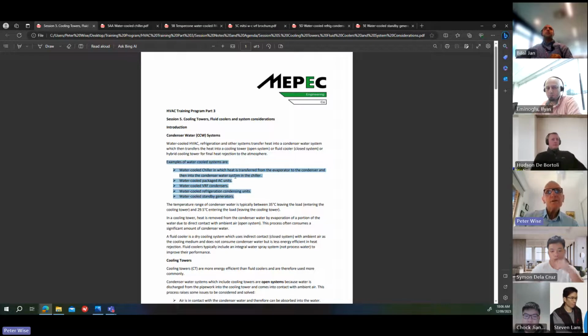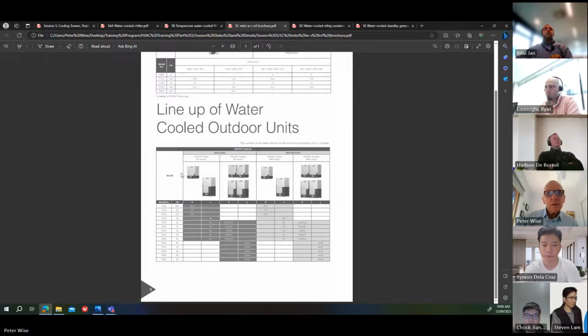Water-cooled VRF condensers. If you've got a VRF system, this is not a very good picture, but these water-cooled condensing units can be located inside the building. You can put them in a cupboard, for instance, or in a plant room, and run condenser water to them. So you don't have a whole stack of air-cooled condensers up on the roof or outside somewhere, and they're more energy efficient.